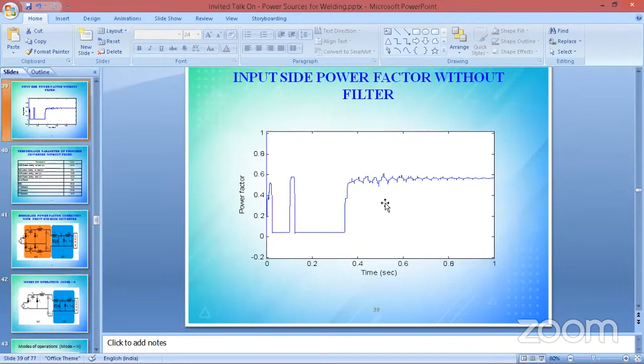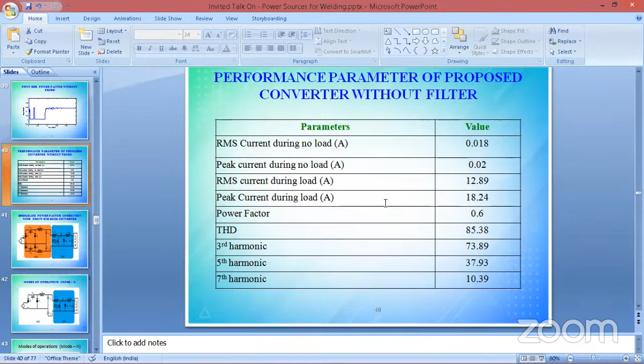The power factor has been brought down to 0.6, and the THD is around 85.38, which is very high. Third harmonic is around 73, fifth harmonic around 35, and there's no need to go beyond the seventh harmonic. So the 3rd, 5th, and 7th play a major role.